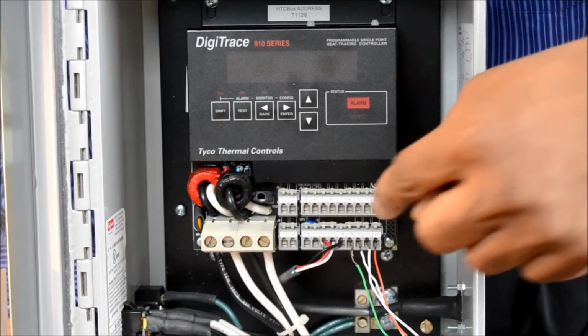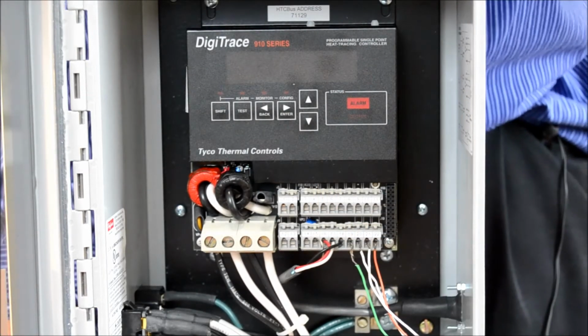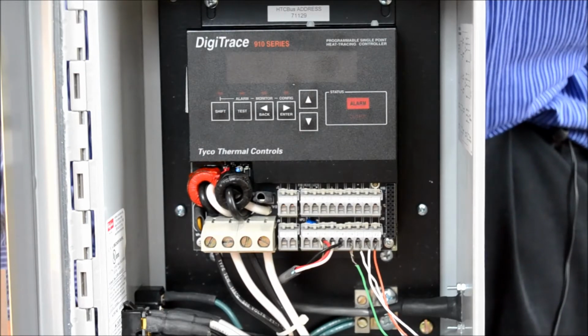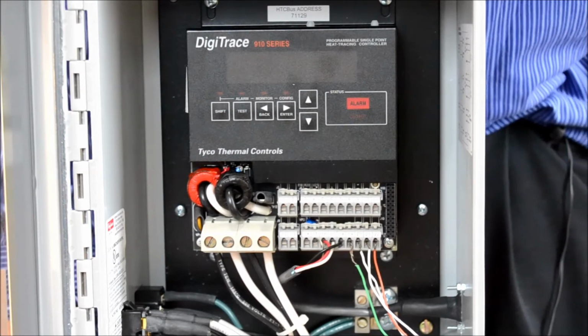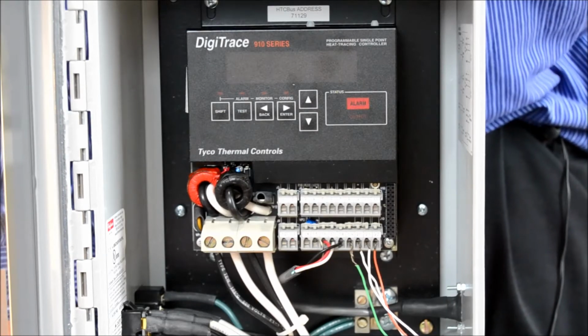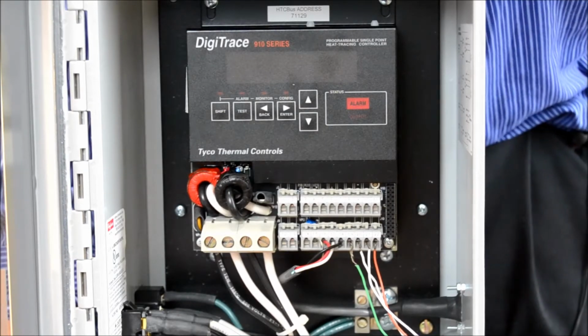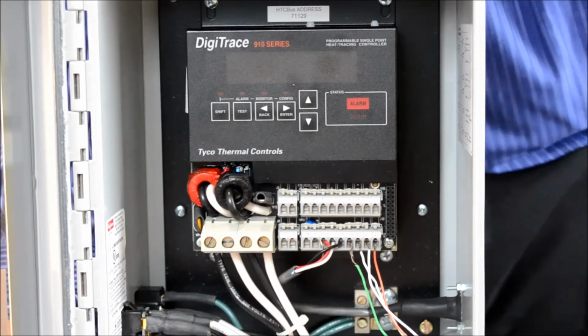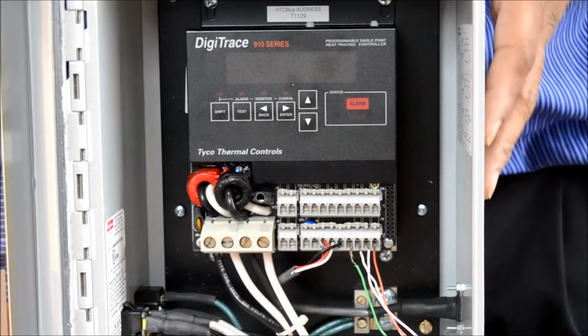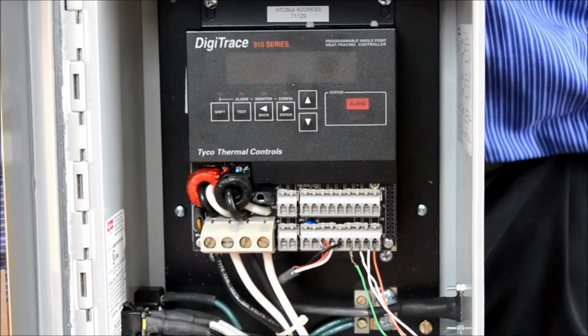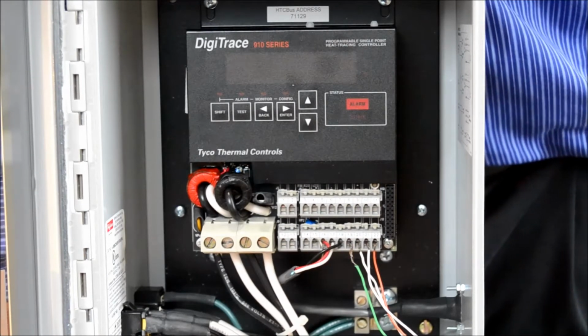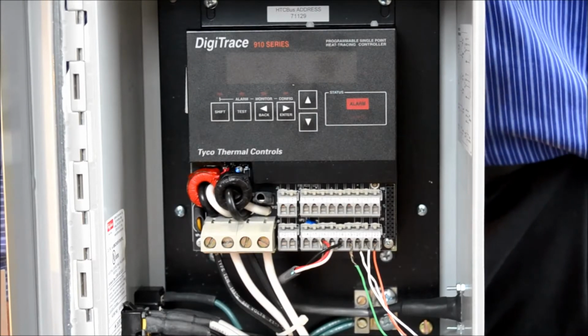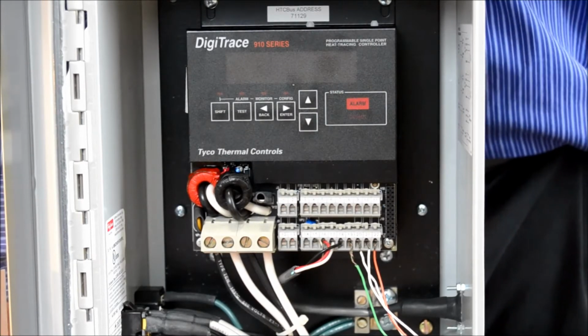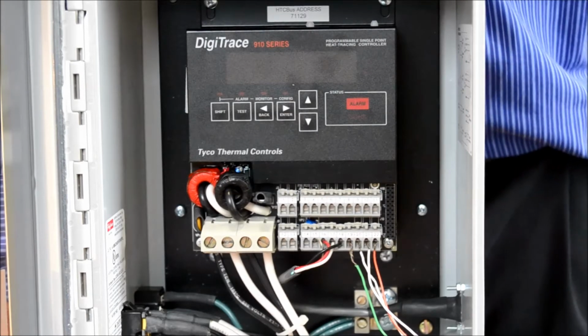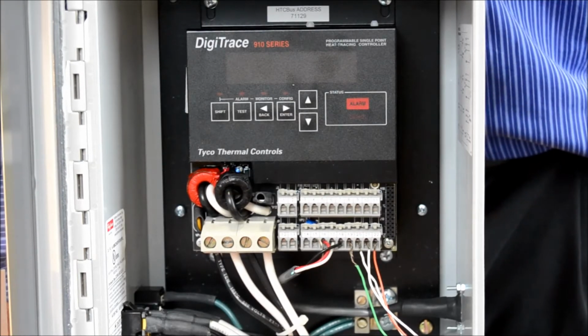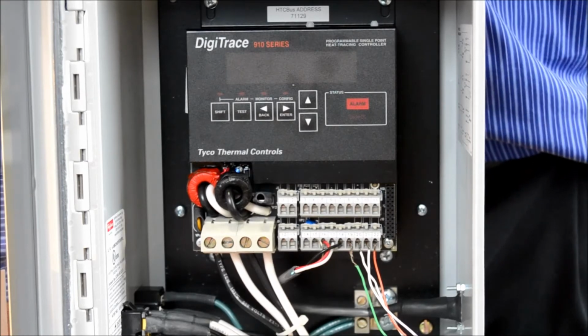Now you also have a feature for an alarm. That's not hooked up right here because it's a demo version, but you can hook this up as an alarm back to the BMS or building management system, or a dry contact alarm as well. Now let's go on to the features. This 910 controller is actually rated for 120 volts up to 277 volts and anywhere in between. So a lot of times people look at the literature and see 277 volts. Well, that's the maximum voltage that this could take, and anywhere in between, like I said before.